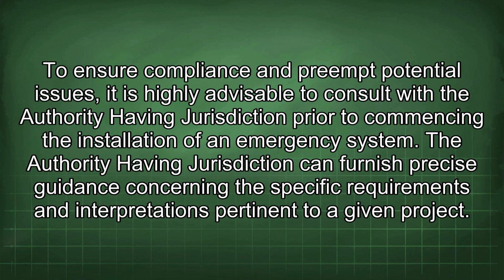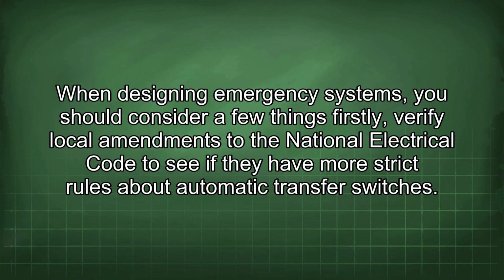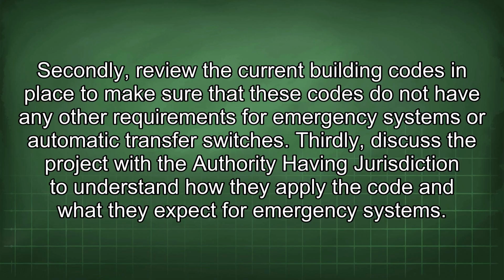To ensure compliance and preempt potential issues, it is highly advisable to consult with the authority having jurisdiction prior to commencing the installation of an emergency system. The authority having jurisdiction can furnish precise guidance concerning the specific requirements and interpretations pertinent to a given project. When designing emergency systems, you should consider a few things. Firstly, verify local amendments to the National Electrical Code to see if they have more strict rules about automatic transfer switches. Secondly, review the current building codes in place to make sure that these codes do not have any other requirements for emergency systems or automatic transfer switches.